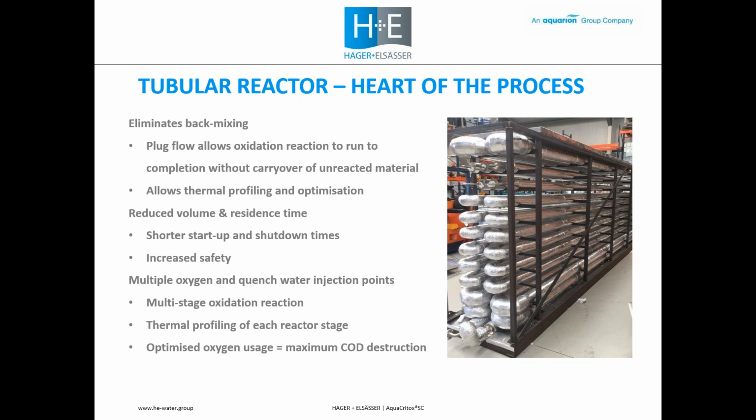So at the heart of the process is a tubular reactor. We don't use a large pressure vessel. This system operates with a single continuous process path. Right from the beginning of the process, the spent caustic will pass through the system, through the heat exchangers, through the reactors sequentially, all the time passing through the same pipe. So there are no issues here with solids deposition. And we can be sure that we have plug flow in the system, so there's no back mixing.